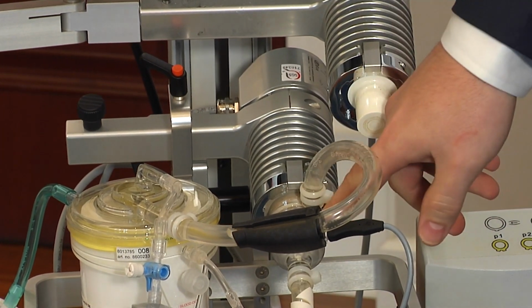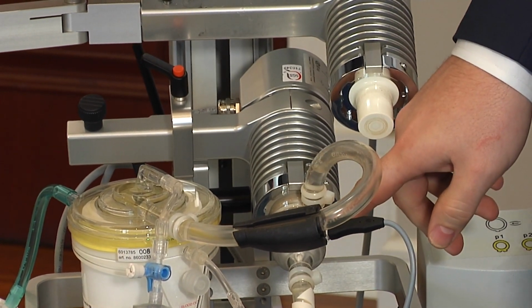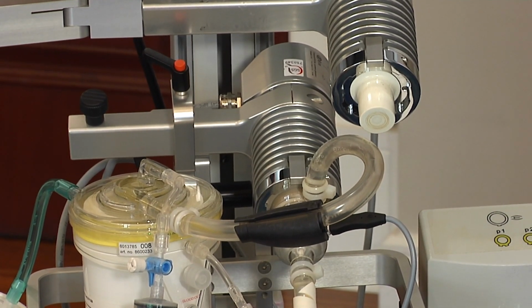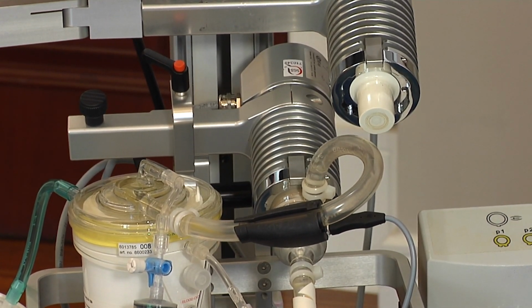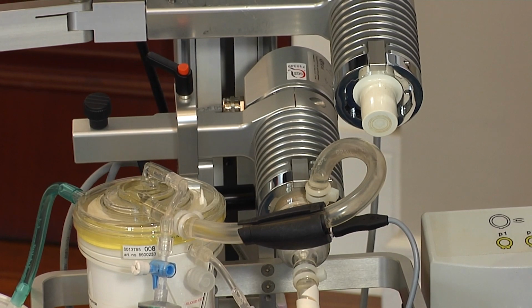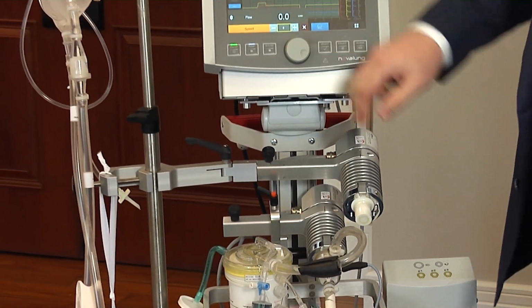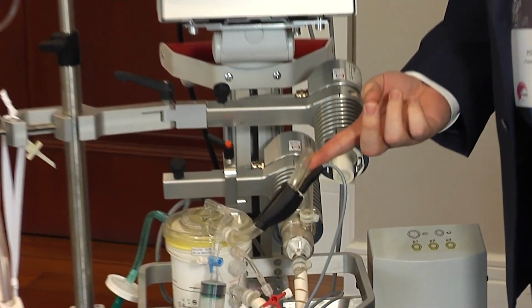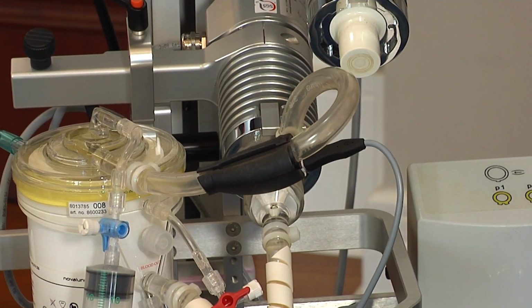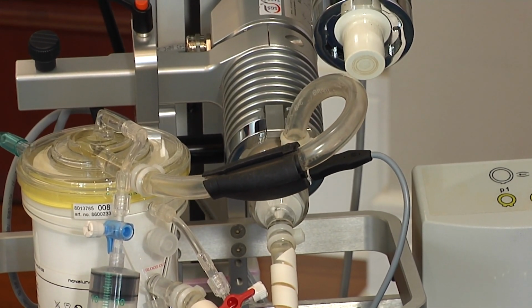All right, so if you see the pump head here, it's full of air, and we have no flow, even though we haven't reduced our pump RPMs. So what I'm able to do is obviously I'll clamp my patient off, but once I drop my RPMs down to 0, I've got one outlet at the top of the pump. The air will rise into the outlet, and the pump will reprime.